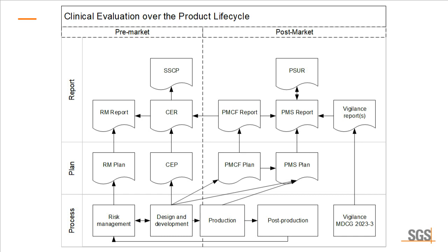The next one, do all devices need CDP? No, the clinical development plan is only needed if you do clinical investigations. So if you find that you already have sufficient clinical data, or if you find that you can have sufficient clinical data without clinical investigation, then you also don't need to have a clinical development plan. You only need to do it if you have at least one clinical investigation needed for your product.